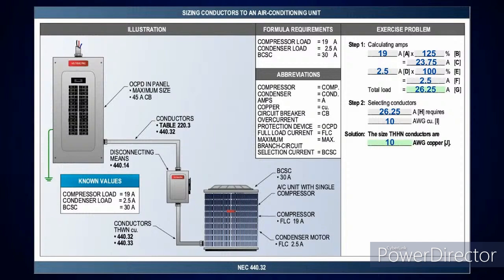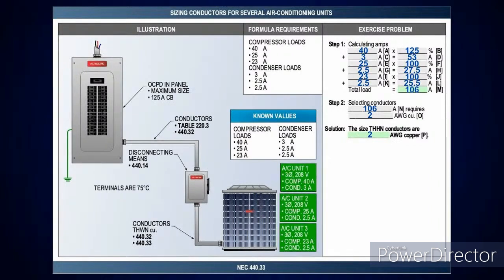Pretty simple. And what you're going to realize is that the AC unit is only going to draw a maximum of that ampacity. So that's how they actually make the nameplate. A lot of people don't realize that they use that same math to come up with what it says on the nameplate. Just because they say 26 amps or 25 amps or 24 amps doesn't mean that unit is going to draw that amount. That's your 125% calculation. So you have to keep that in mind as a reference point.